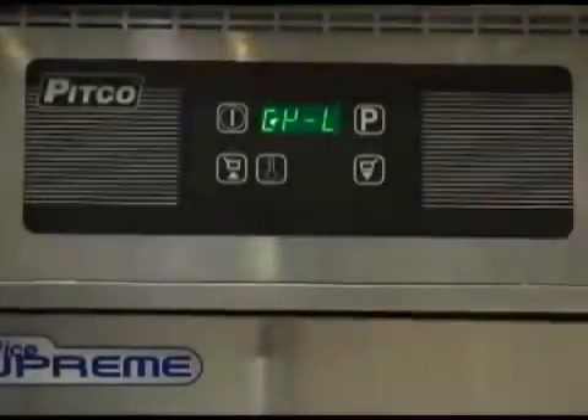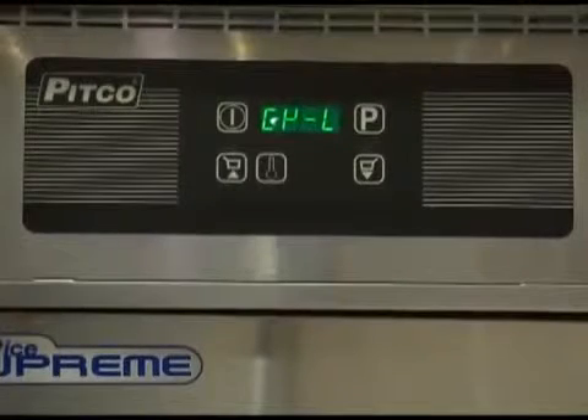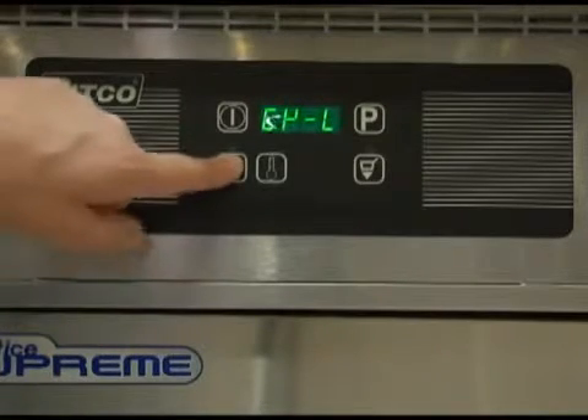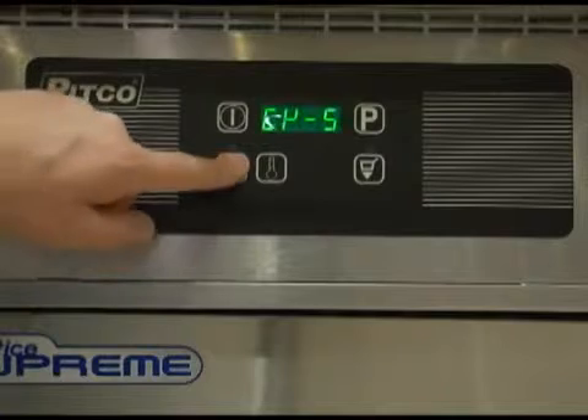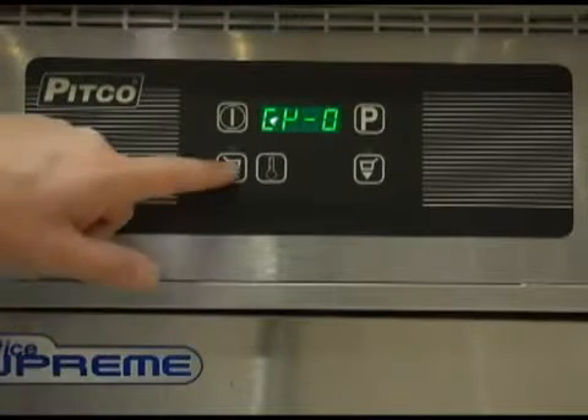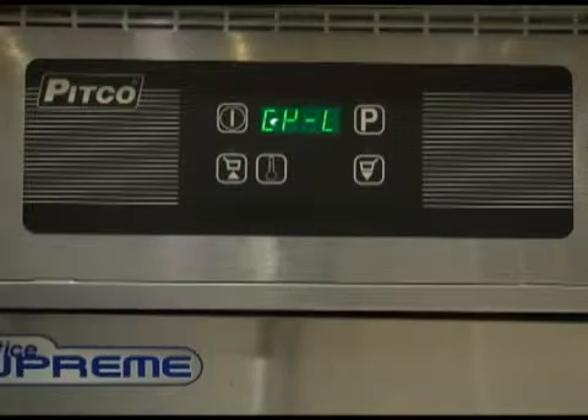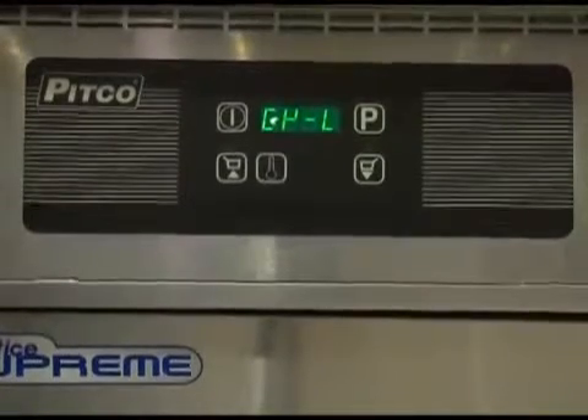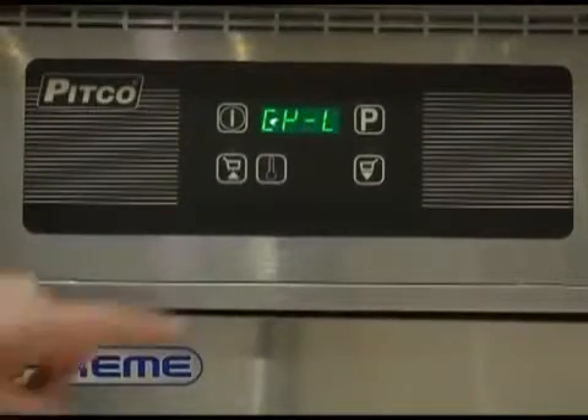The display should now show the current setting for the melt cycle. CYL is for liquid, CYS is for solid, and CY0 is for a no melt cycle setting. Once set to the correct setting for your shortening type, press program to save and move on to the next option.